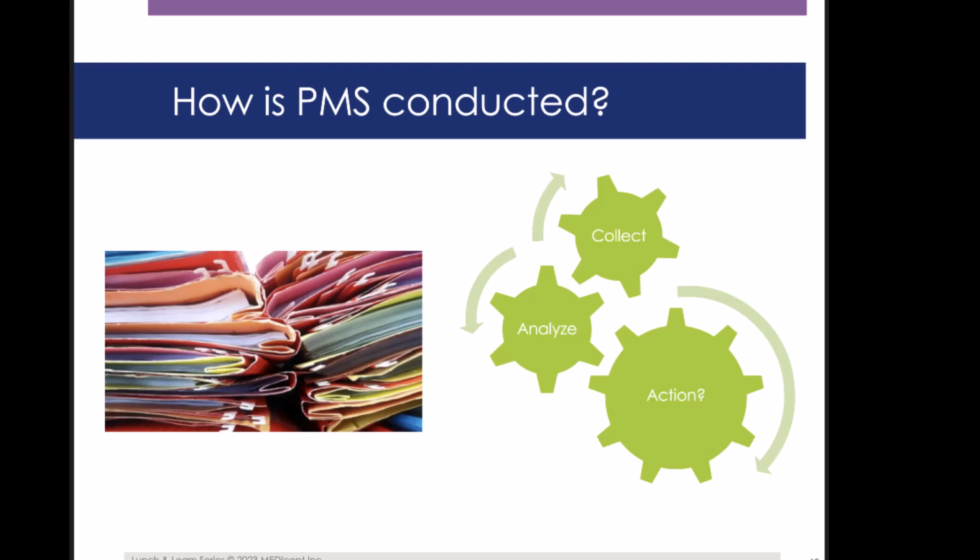There are quality management system processes that contribute to a device's post-market surveillance process. These processes include nonconformances, internal audits, complaint management, and CAPAs. These processes are important and provide the framework for post-market surveillance. However, manufacturers often make the mistake that these are the only data sources and activities that need to occur. In doing so, they are missing out on valuable data that will contribute to detecting issues and identifying improvement opportunities.